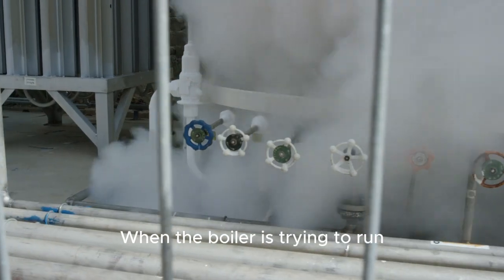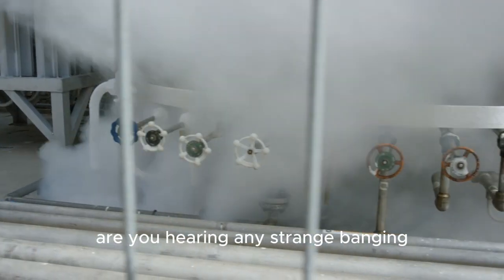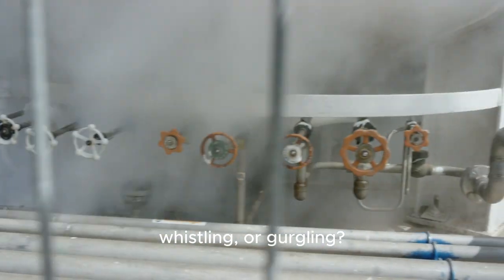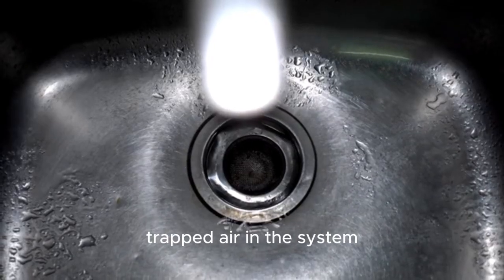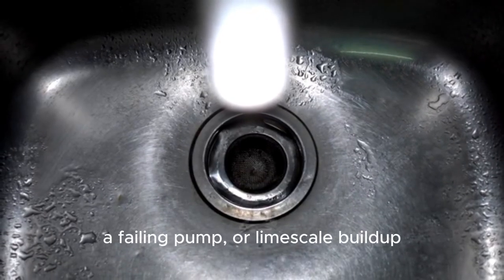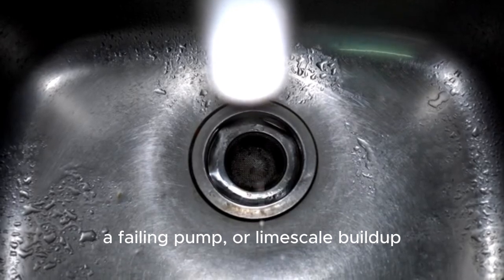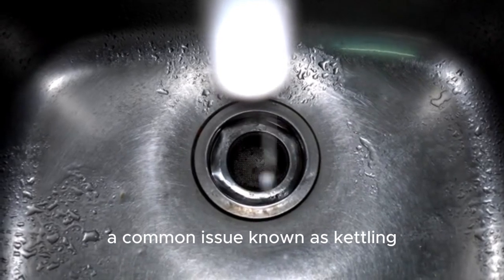Step 6. Listen for unusual noises. When the boiler is trying to run, are you hearing any strange banging, whistling, or gurgling? These sounds can indicate trapped air in the system, a failing pump, or limescale buildup, a common issue known as kettling.